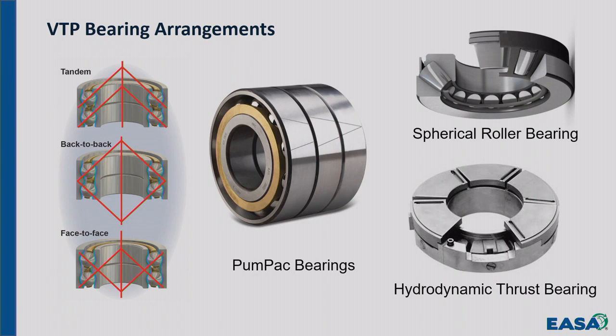If the motor goes back on the same pump. Many customers will swap motors around, okay? And different pumps may be configured differently. They may be very similar pumps, and the same motor would fit on two different pumps, so they got one spare for the two. But this one's pumping one application, and that one's pumping a slightly different application, and the head and flow characteristics are different. And this one's a different depth, and it has different axial thrust than that one. And they don't tell you that they switched the motor from one application to another. They just tell you the bearing's now running hot. And the bearings should have been configured differently.